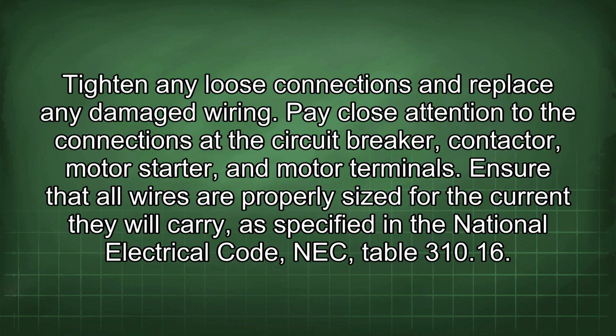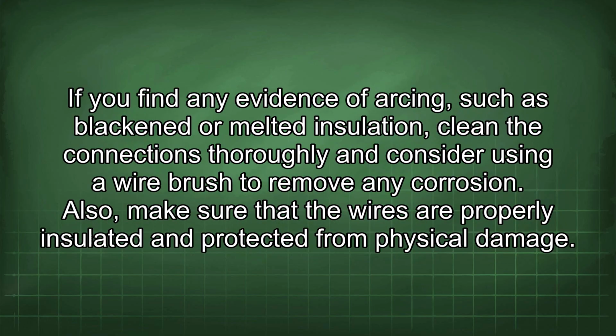Ensure that all wires are properly sized for the current they will carry, as specified in the National Electrical Code, NEC, Table 310.16. If you find any evidence of arcing, such as blackened or melted insulation, clean the connections thoroughly and consider using a wire brush to remove any corrosion. Also, make sure that the wires are properly insulated and protected from physical damage.